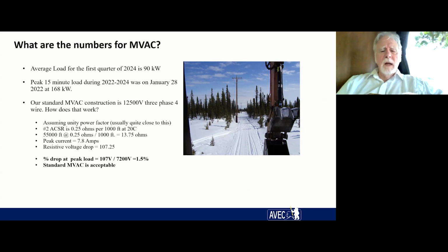The other thing that I tried to look at here was using our minimal standard for AC line construction, which is also something Darren touched on, but also repurposing it for DC, MVDC transmission, just seeing how that works in this instance with that load. So we assume number 2 ACSR, that's aluminum conductor, steel reinforced. It has a certain resistance, and we have 55,000 feet of total line that has to be built.